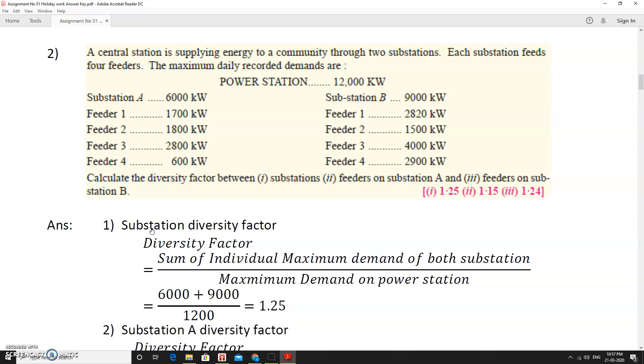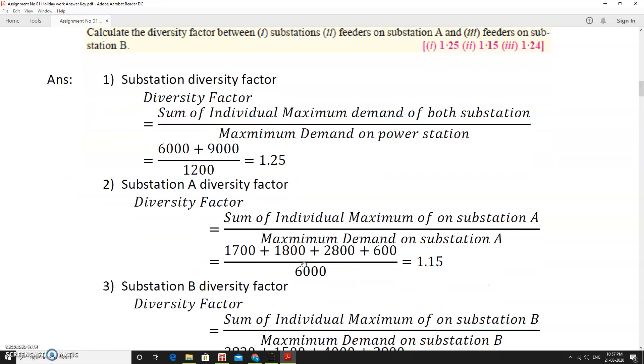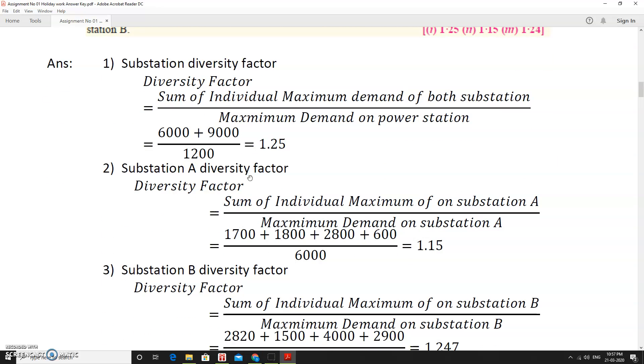To calculate the diversity factor at the power station, we take the sum of individual maximum demands of both substations: 6,000 + 9,000, divided by the station maximum demand of 12,000 kW. This gives a diversity factor of 1.25.